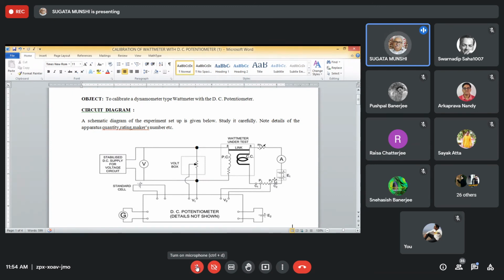Those terminals P1 and P2, they shouldn't have been shown there, but P1 should have been here, P2 should have been here - that is the proper way. Unless that is done, your intention will not be clear. So current leads in and leads out through the current terminals, and the voltage is measured between P1 and P2. So P1 is here, P2 is there. Therefore, there are contacts at P1 and P2. Contact resistance will also form at P1 and P2. Why shouldn't they cause any error?